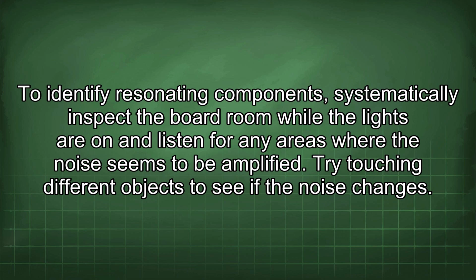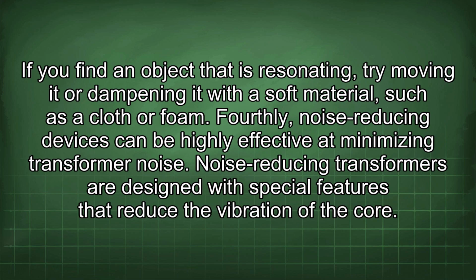To identify resonating components, systematically inspect the boardroom while the lights are on and listen for any areas where the noise seems to be amplified. Try touching different objects to see if the noise changes. If you find an object that is resonating, try moving it or dampening it with a soft material, such as a cloth or foam. Fourthly, noise-reducing devices can be highly effective at minimizing transformer noise.